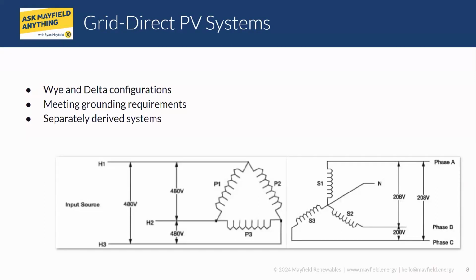And I believe, Medina, when you get into some of the things on the rectifiers and the battery storage systems, that'll come up a little bit more. But sometimes, even if it's a 480 to 480, if it's providing that isolation, it does protect the system. So that's important. It also gives you the opportunity, as you're seeing here, like on the Delta Y, to have a separately derived neutral. So it isolates the two systems there.